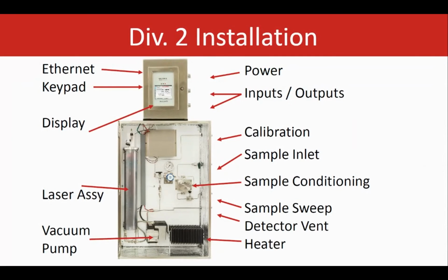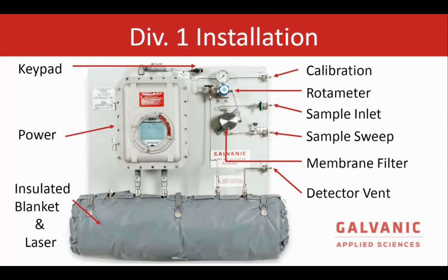As mentioned earlier, the unit is certified for a variety of hazardous area classifications. This one here is the DIV2 unit. You can see the sample conditioning system on the right side, as well as the Herriott cell and the optics, with the cell components in the enclosure. The size and design are very accessible and easy to work with. If there's any replacement needed, it's easy to work with. This one here is another AccuLase, but this one is a DIV1. Again, on the right side you see the sample system, the optics and sample cell enclosure. Everything is shown in this picture, so you see a lot more detail about where every part is located.